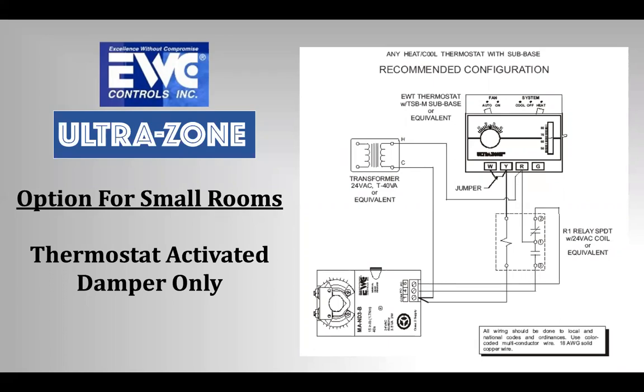Install a damper to that area, install a thermostat to that area, install a transformer to provide power to one or both of those items, and my damper will open and close based on the thermostat. Now, I will not energize equipment in this case, but I will open if I need to based on my setting, and I will wait for a heating or cooling call in other areas of that house. Now, let's be honest, if that bonus room is calling for heating or cooling, it's not going to be ignored for very long because you will have calls in other parts of the house.